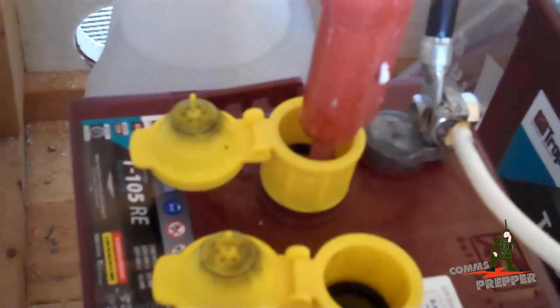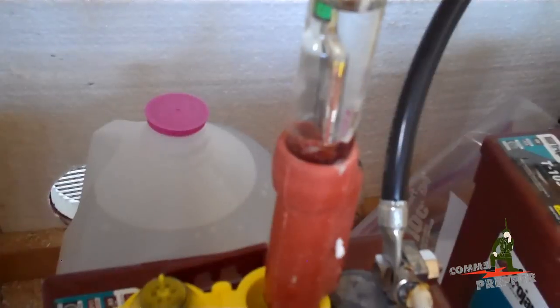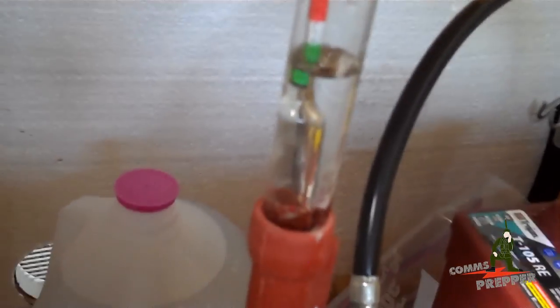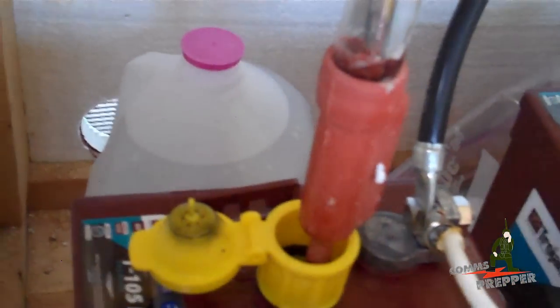What I do is I take a little sample of the electrolyte solution, suck it up into the hydrometer here and read where the water level falls on that scale in there, and I'll repeat this for all 12 cells.